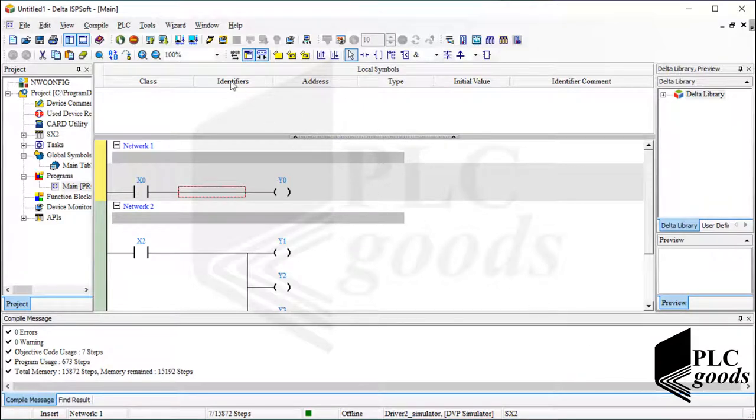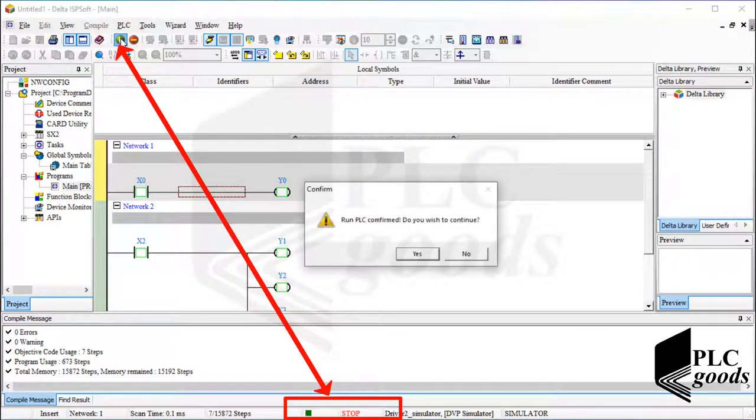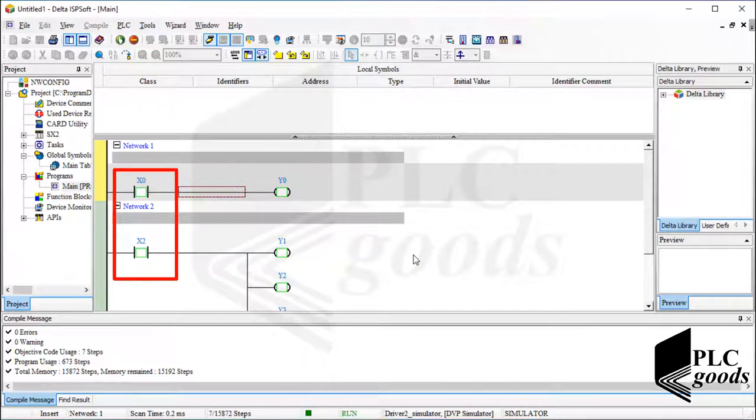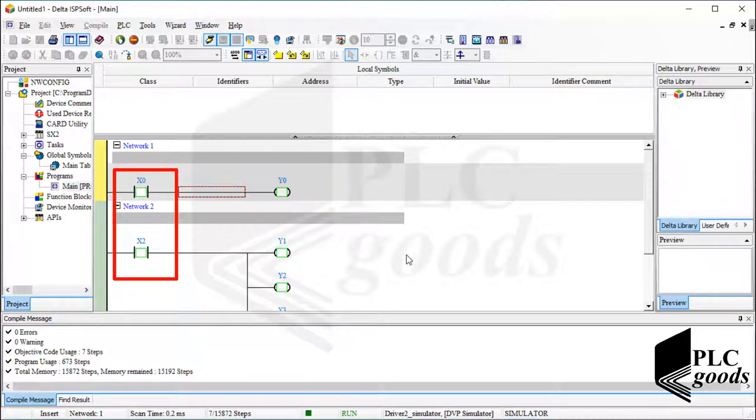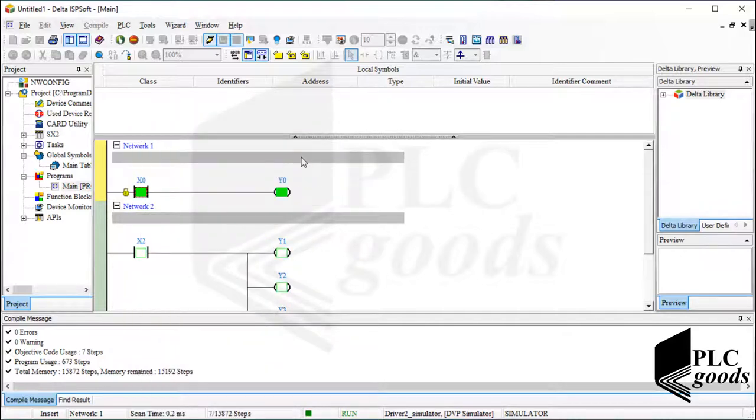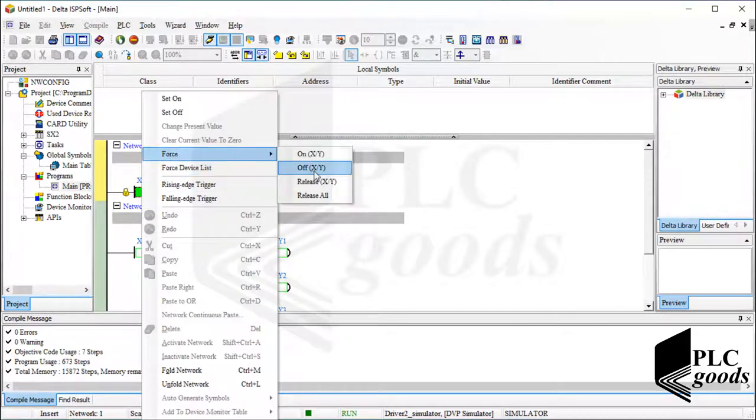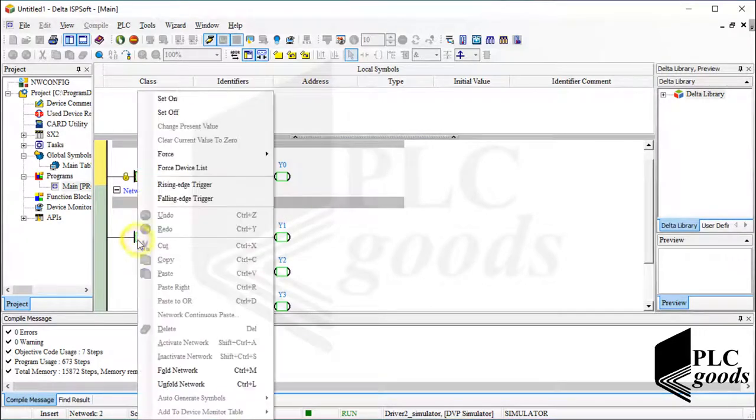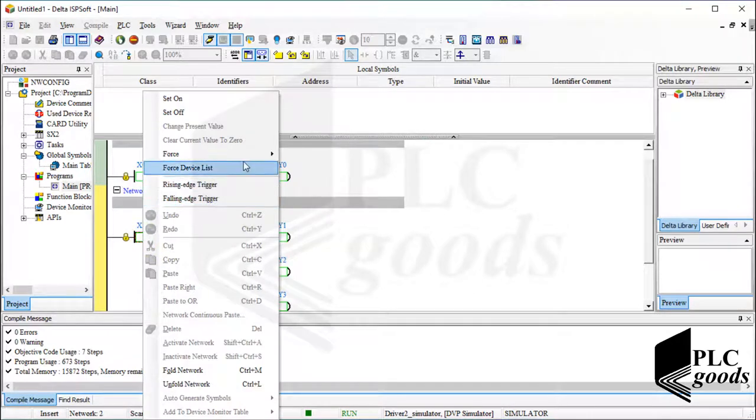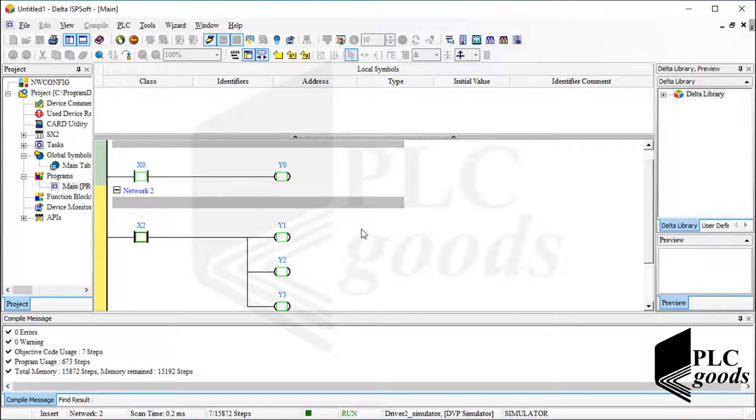Now let's activate the online mode and run the virtual PLC. Naturally, there aren't any real connected switches or push buttons to change digital input addresses. At this time I can right click on digital input addresses and use these force items. Note that these items can be used when a real connected switch or push button is broken. Note that when a forced state is selected for a digital input address, this lock will appear, and PLC won't use the real state of the digital input address. To remove all forced state, we can use release items. Alright, let me stop the virtual PLC and exit from the online mode.